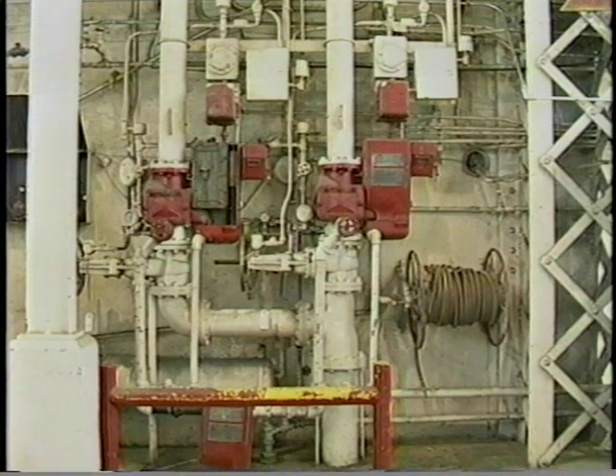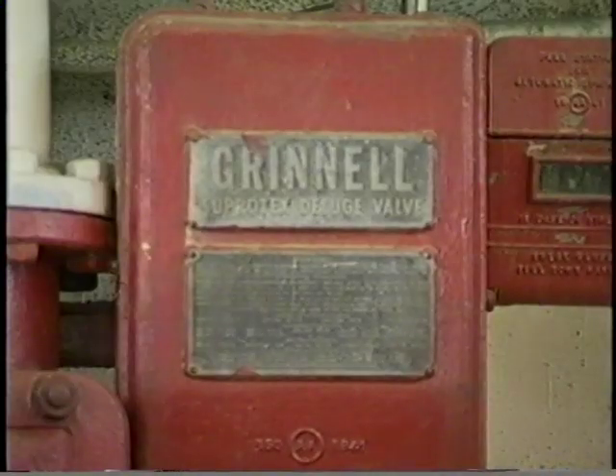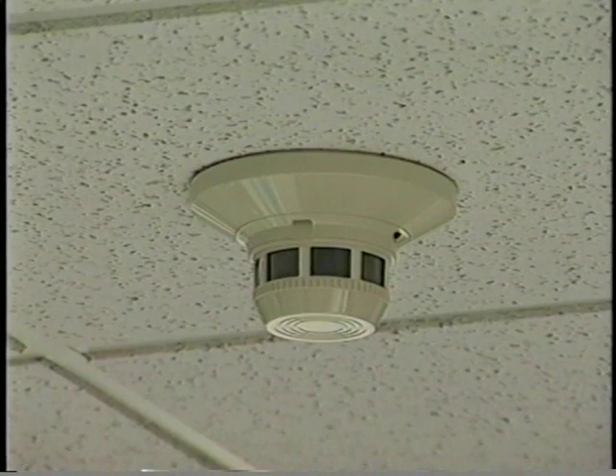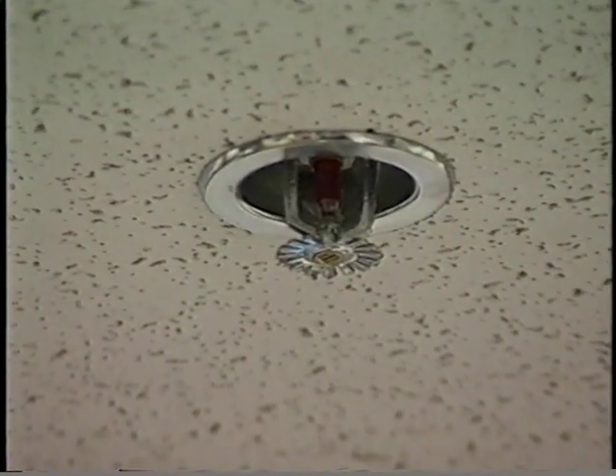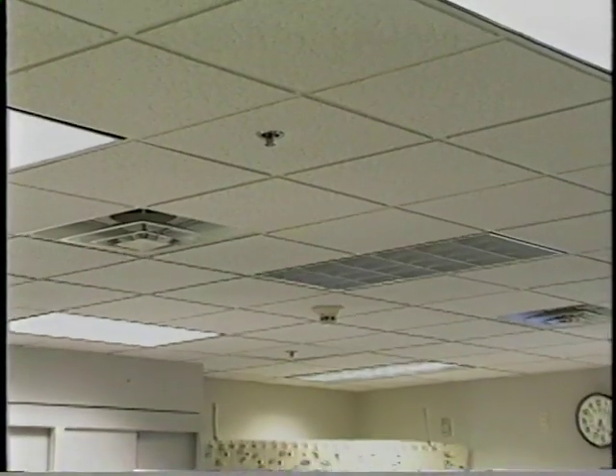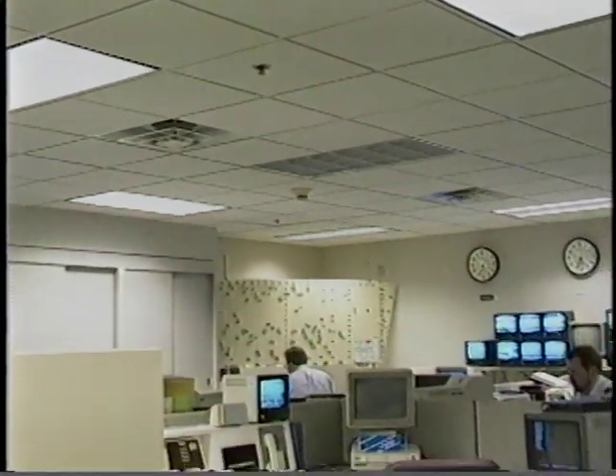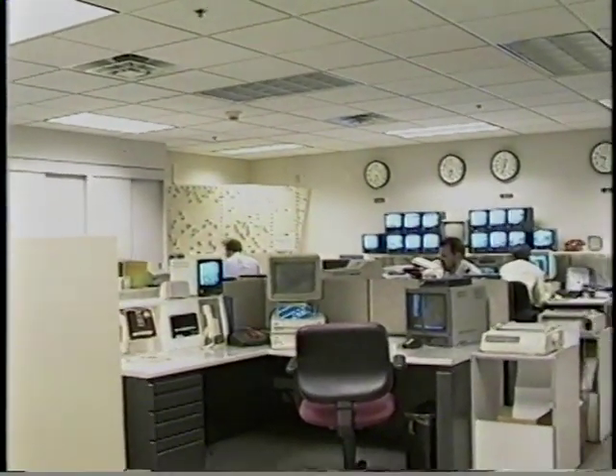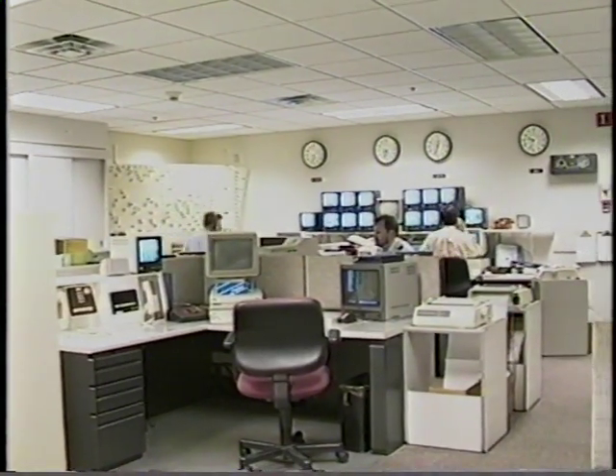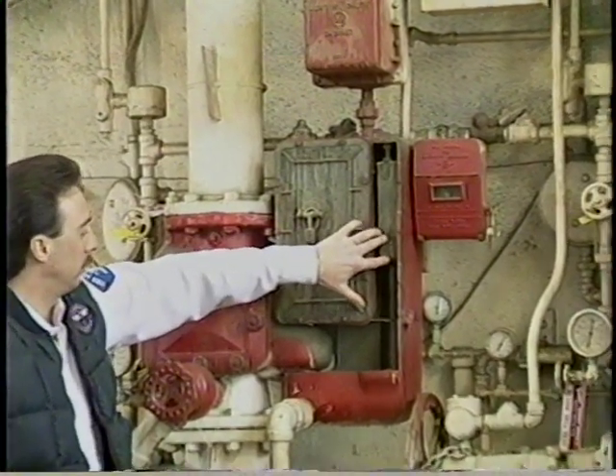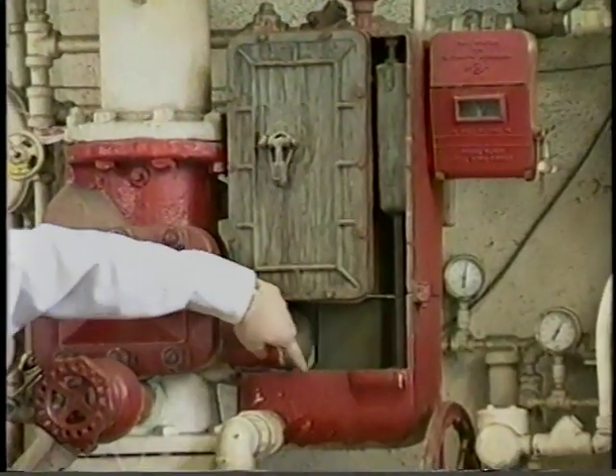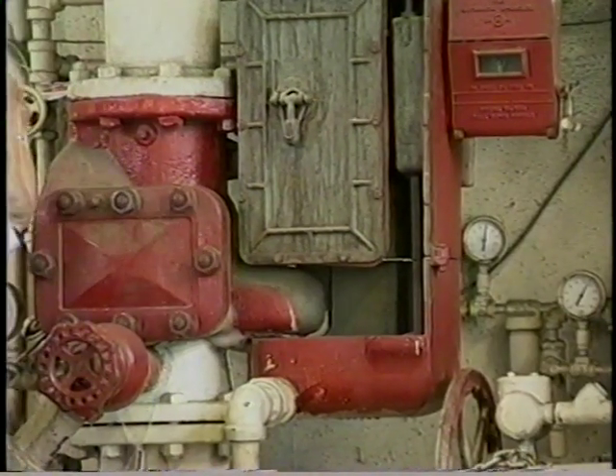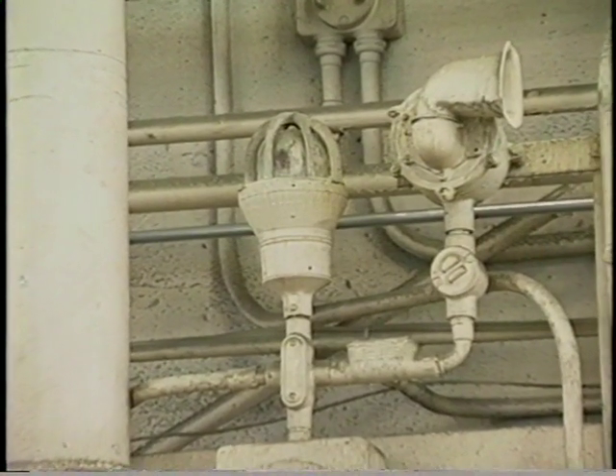A pre-action sprinkler system is a dry system with a deluge-type valve, fire detection devices, and closed sprinklers. This type of system is used in areas where water damage must be prevented, even if a pipe breaks. The system will not discharge water into the piping unless a heat or smoke detection system is actuated. When the detection devices are actuated, the deluge valve opens and water flows into the system. An alarm sounds a warning prior to the opening of the sprinklers.